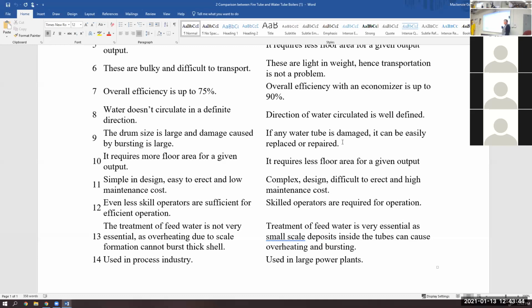These systems, partly because we're getting to higher pressures, higher temperatures, and higher energy, carry more risk. You need more skilled operators and more training for performing maintenance. Even though the water tube itself is easier, water treatment is a huge factor—you have to prevent scale or corrosion buildup inside the tubes, so you usually need a small chemical treatment plant for the incoming water. Whereas with fire tubes, it's less of an issue since you're not touching as many surfaces inside each tube.